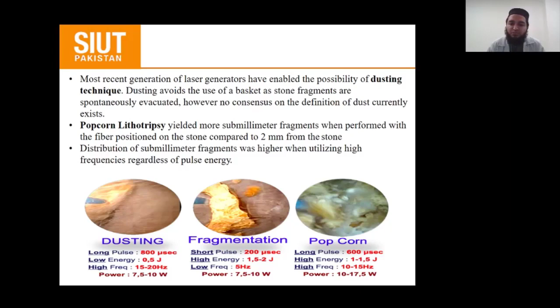So in dusting, we can see that the pulse is long and the energy is low. However, the frequency is high. Whereas in the popcorning effect, the pulse is long, but the energy and frequency, both of them are high. So for popcorn lithotripsy, the energy setting and the frequency setting should be high.